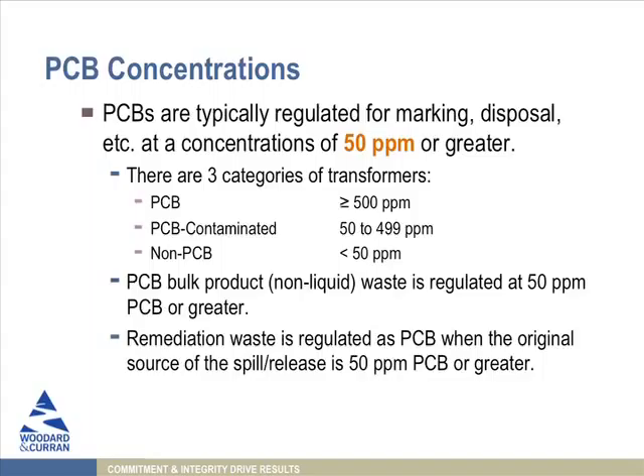One is if you're between 50 and 499, then you are considered to be what's called PCB contaminated. And you have to pay attention to those equipment, those transformers. The most important one is if you have PCBs at 500 or above. And in that case, the regulations impose a considerable amount of scrutiny and requirements. So those are the key levels to be always thinking about in terms of everything we're going to be talking about for the next little bit together.